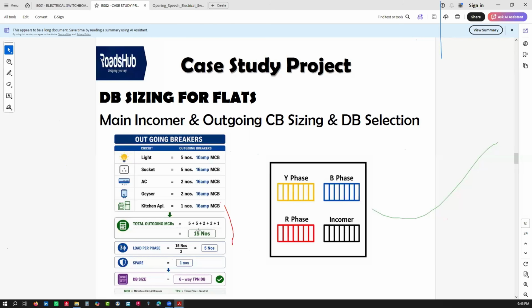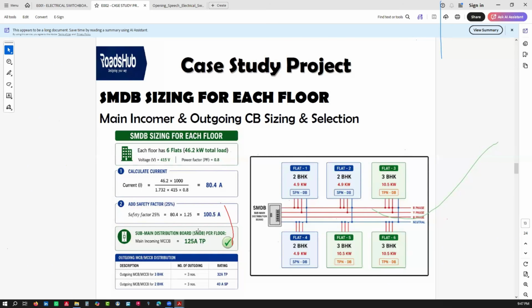The other one, we didn't do a factor of 3 because that was a single pole, just red phase and neutral. So you just maintain the same line because all of them are being supplied from a single phase. But for a 3-phase, we are supplying from 3 different cables. So you need to be very careful when you're doing DBs for 3-phase, because if you don't divide by 3, you will go buy the wrong thing. Now this design, I haven't even started drafting these things. And that's the aim. You now come to the cards, the different cards we have, and then you can come up with your design because you've actually developed a proper sizing protocol that will make you a very perfect engineer. Now, you want to come up with an SMDB.